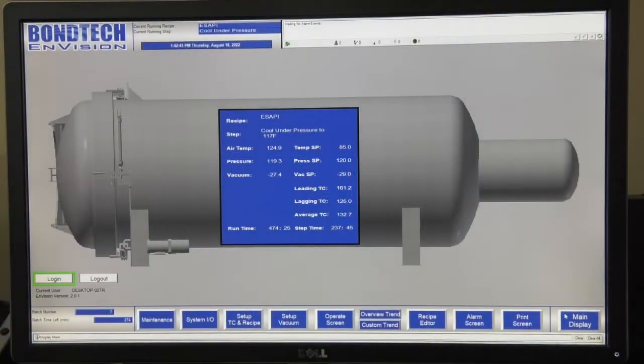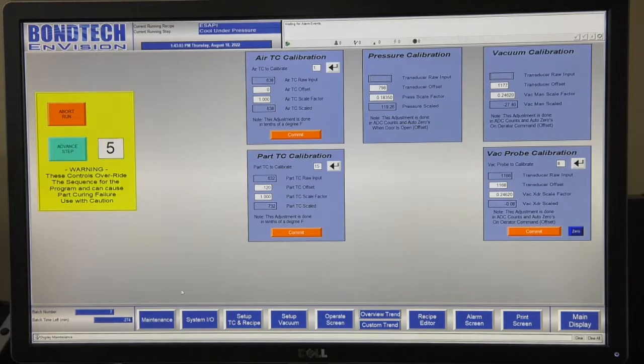This is the main page of the operator screen, just giving what recipe it is, what the thermocouples are doing, what they are reading, as well as the vacuum system. And it also tells you how much time is left in that particular recipe. Moving over to the maintenance screen, this is how you would calibrate for your maintenance and our technicians, showing what the air TC calibration is, pressure, vacuum, as well as the individual part thermocouples within the system.